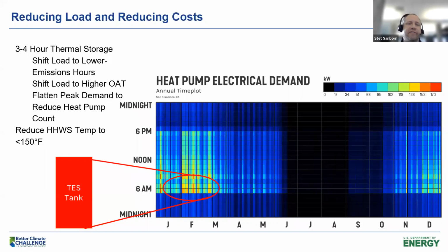So we could save a significant amount of cost because, across the rest of the year, the peak load is not that high. Sizing for a peak occurrence that's very short in duration is not what we want to do for a cost-effective design. So I encourage everybody to think about thermal energy storage or targeting appropriate warm-up start times to right-size their heat pump applications.